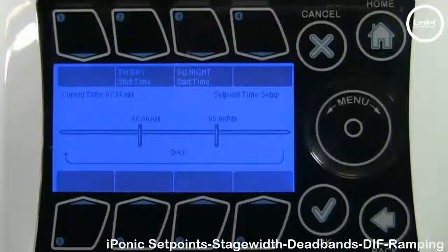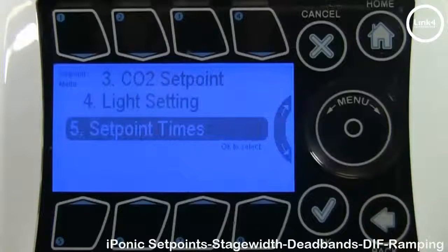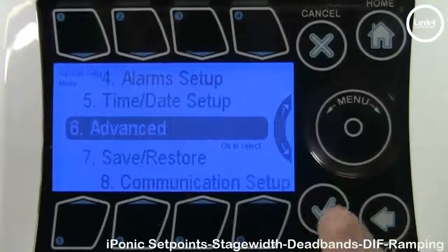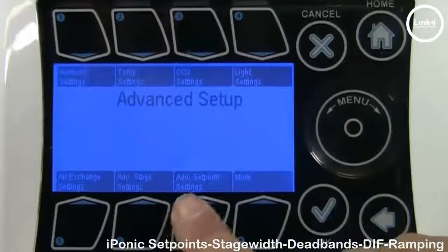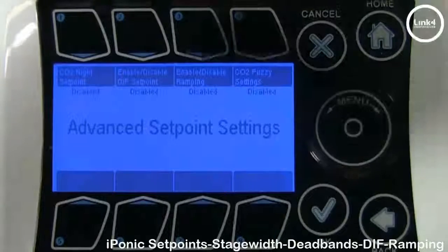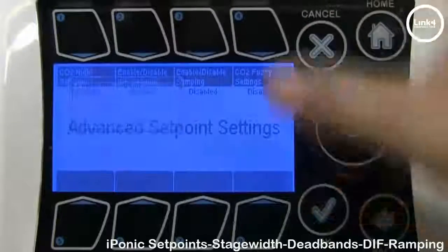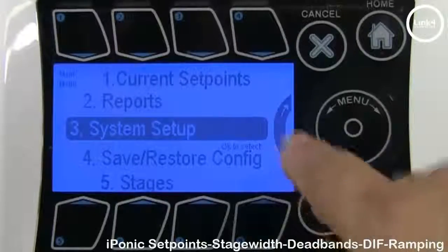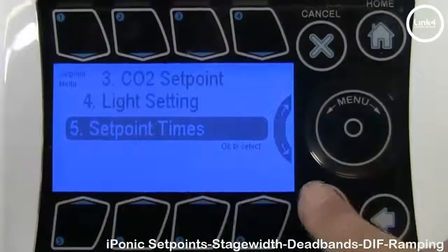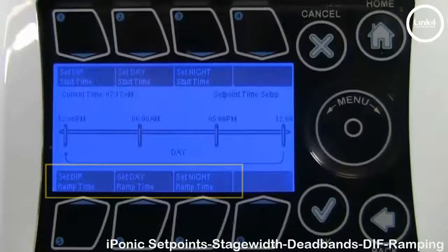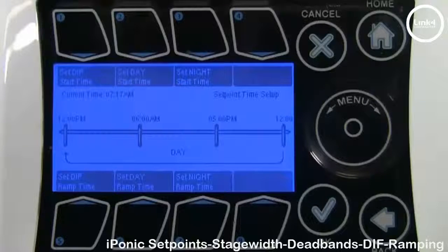To enable these features, hit back twice, then go to system setup, go to advanced setup, and then go to advanced set point settings. As you can see, your DIF and ramp is currently disabled. Go ahead and enable DIF and ramping, then hit the home button, save it, and hit OK. Go to your set point screen and then go to set point times. In the set point times screen you will now see more options at the bottom, as well as an option to input your DIF start time.